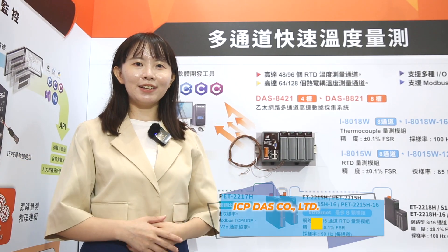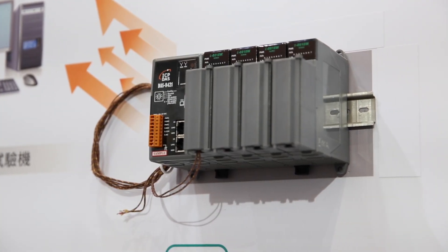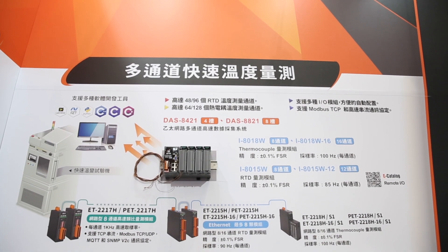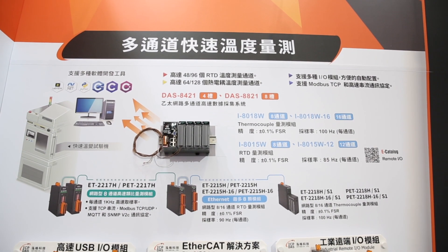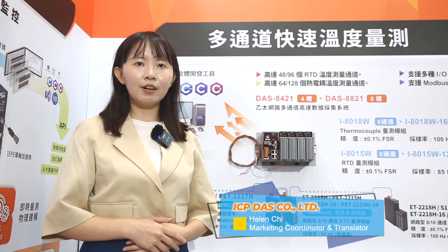Hello, I'm Helen. Our new DAS8000 series creates a multi-channel high-speed data acquisition system. The system helps staff to efficiently acquire temperature data from the IC test handler. The series supports up to 96 RTD channels and up to 64 to 128 thermocouple channels. The sampling rate of each channel can be as fast as 100 Hz.